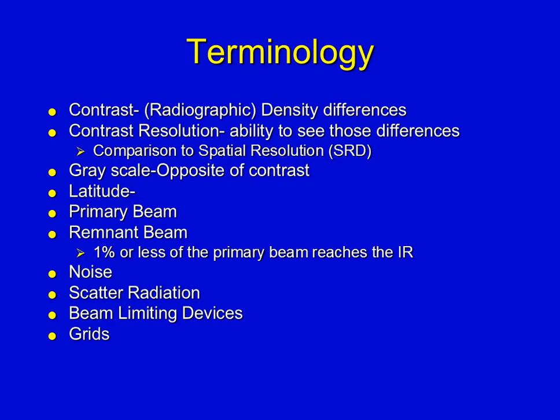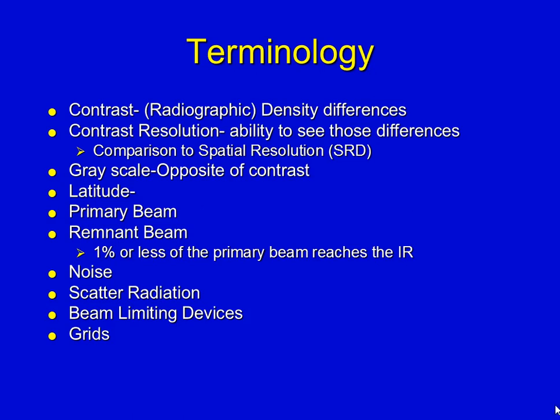Beam limiting devices are anything that contains your beam to a specific size — collimators and diaphragms are different types. Grids are a device we use to clean up scatter after it's created; we place the grid between the image receptor and the patient to remove some scattered radiation before it strikes the image receptor.